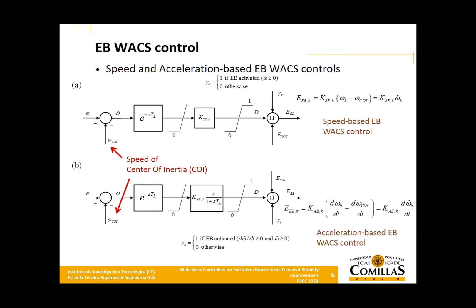We have two options to modulate this external voltage added to the field winding, done using an IGBT with a certain duty cycle. We can use the speed deviation or the acceleration — which is the derivative of speed. In the paper, you have a formal proof of these schemes based on the Lyapunov energy function.